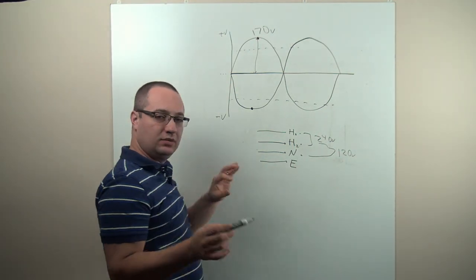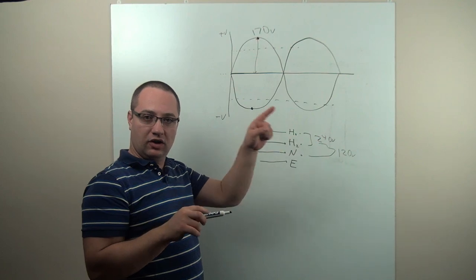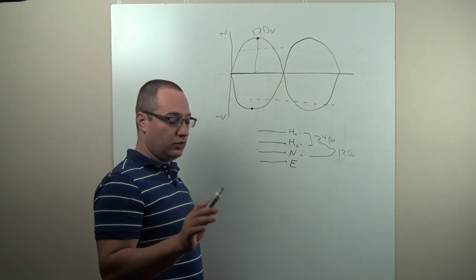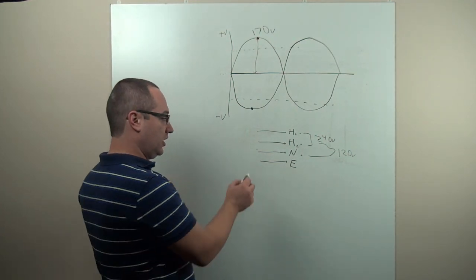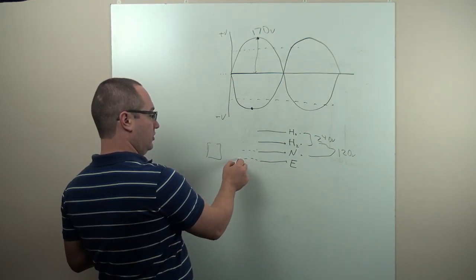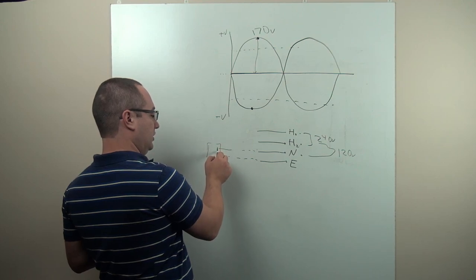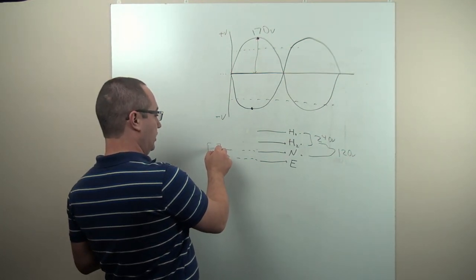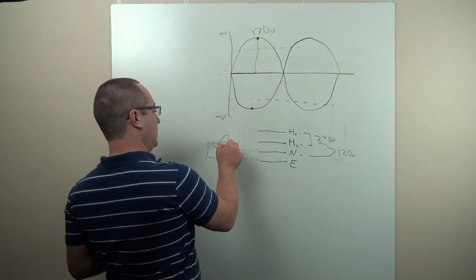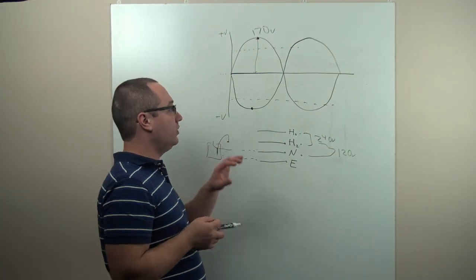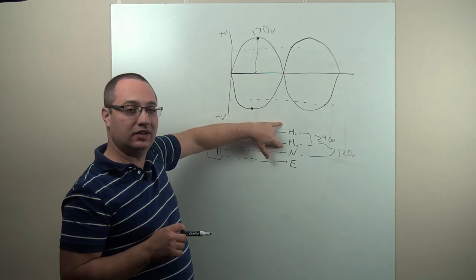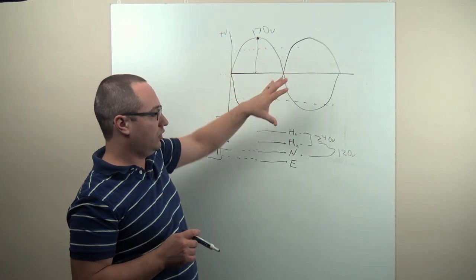earth and neutral tend to be tied together in the electrical panel of your house. It does not mean that earth and neutral are interchangeable because they serve different functions, but they are tied together. If you follow the neutral all the way back to the electrical box and the earth all the way back to the electrical box, they will be sitting attached to the same rail, and that same rail is attached to the neutral line that comes out of the transformer, and that same line goes outside and gets hammered into the ground.